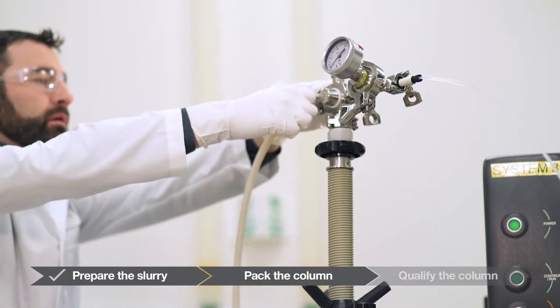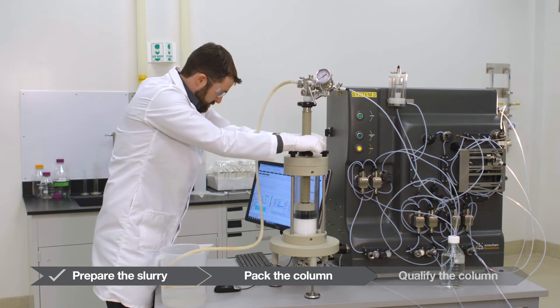After the bed is formed, close the column outlet and displace liquid through the top of the adapter to waste using the bypass line. Bring the adapter into contact with the top of the bed without pushing the resin over the o-ring. POROS resin does not shrink or swell, so an open head space is not recommended. Flow at the packing flow rate again for one to two column volumes, taking note of the bed height at the desired pressure. Adjust the adapter as described in the previous step to the noted bed height by displacing the liquid through the top of the adapter and to waste.